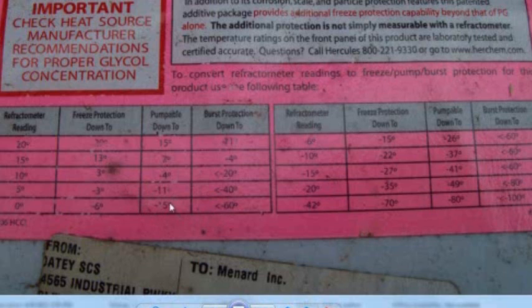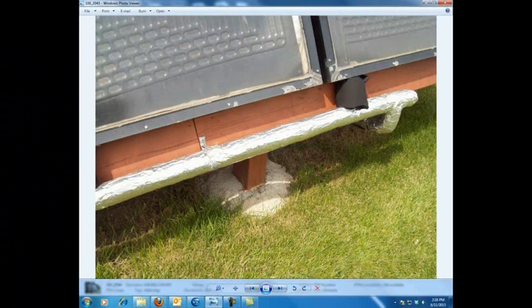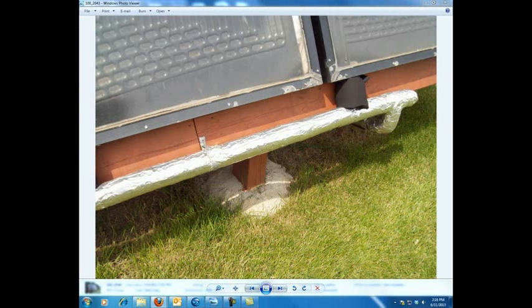The real key is I can pump down to minus 15 degrees — but it comes at a trade-off. The interesting thing about glycol is that it is more viscous than water. It tends to weep and pour out of places. You may have a tight seal and all of a sudden you're seeing little bits of this red glycol slowly getting through. And because it's more viscous, it's a little bit harder on the pump.